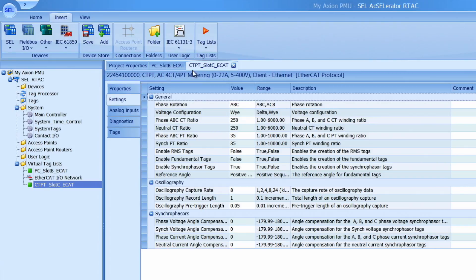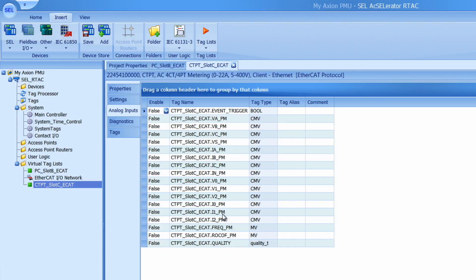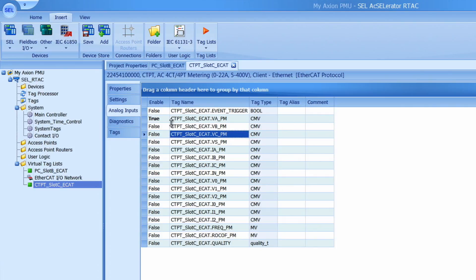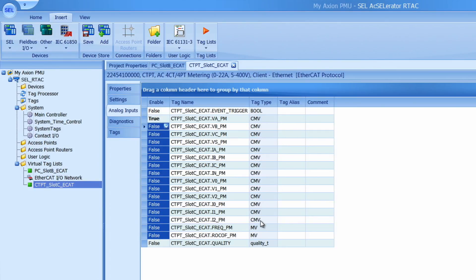The next step is to go to our analog inputs tab and enable each individual phasor that we want to work with from the module. By default all of these are disabled. All we have to do to enable them is set them to true. You can do that by turning one to true and then if I select it and hit ctrl c to copy it and then paste over the rest of my phasor modules. I can hit ctrl v and enable every phasor quantity I have.